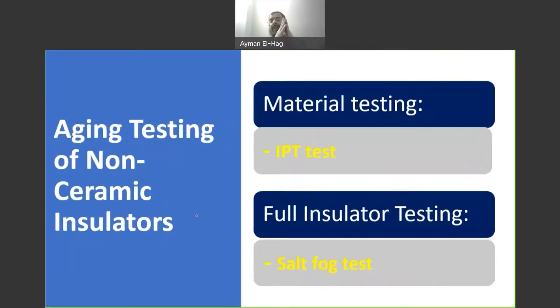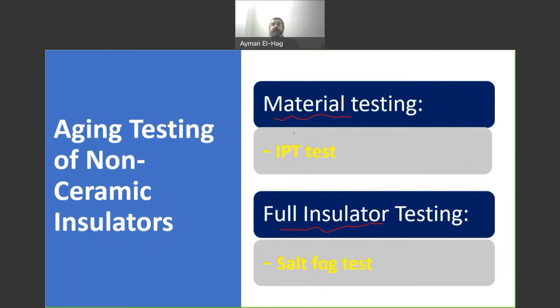When it comes to the test, we have two main classes of tests. The first one is called the material test and the second is the full insulator test. In the material test, we bring samples of the materials and test them without the full insulator. The most common type used to test the material is the IPT test, which is used to screen materials and evaluate their erosion and tracking resistance when subjected to dry band arcing.